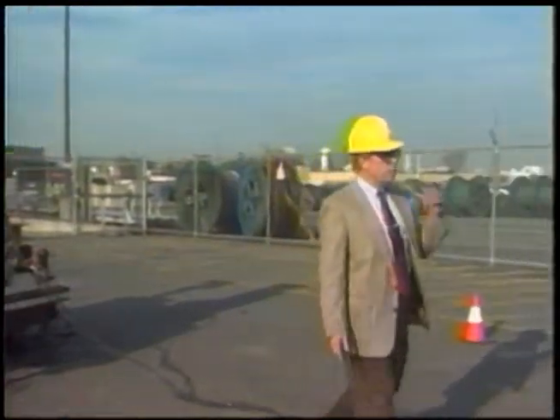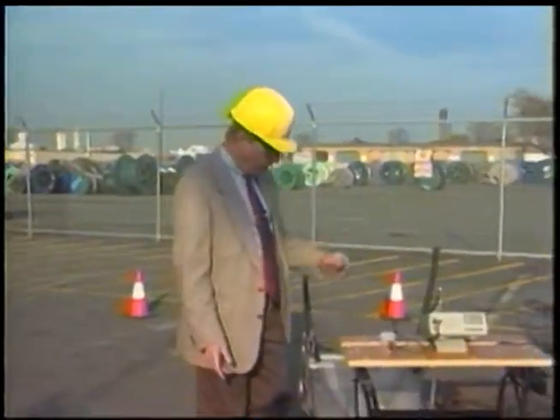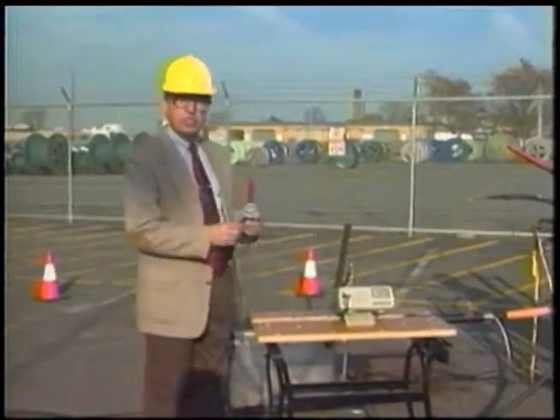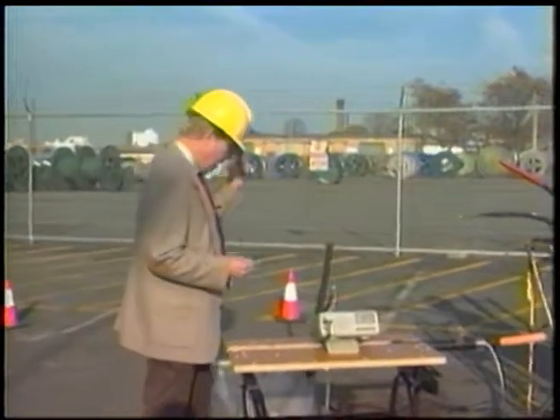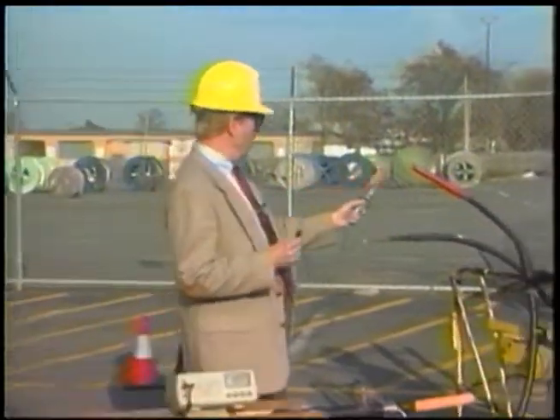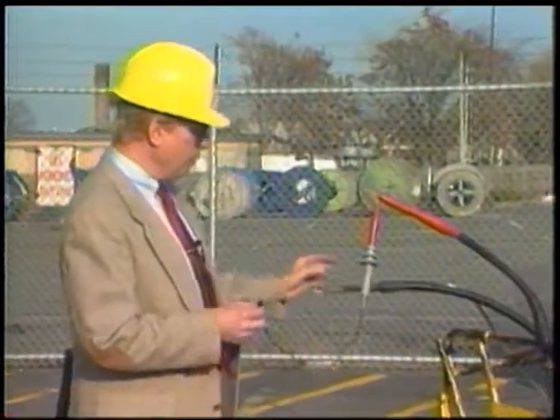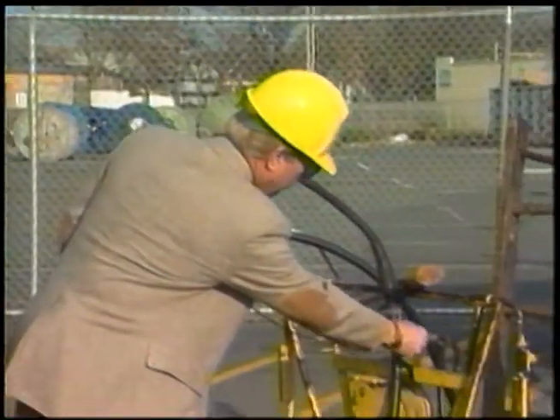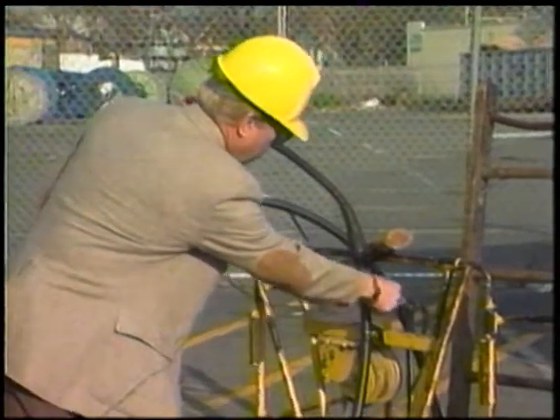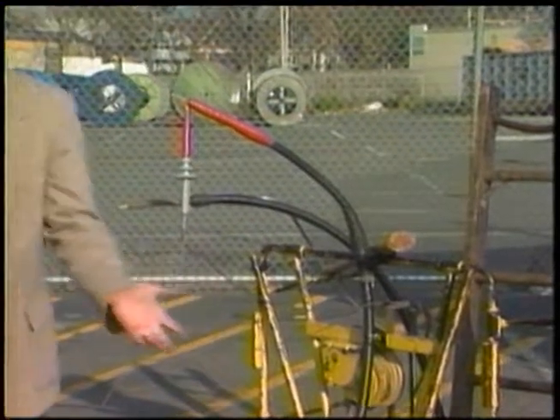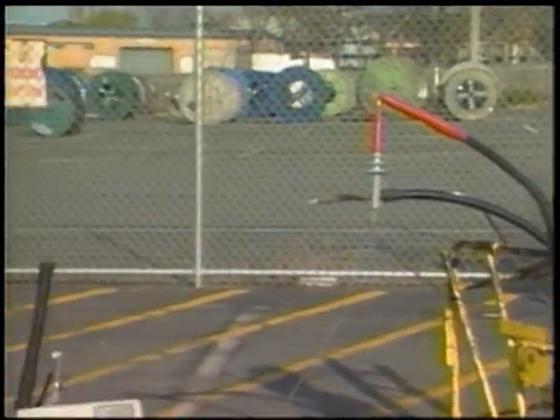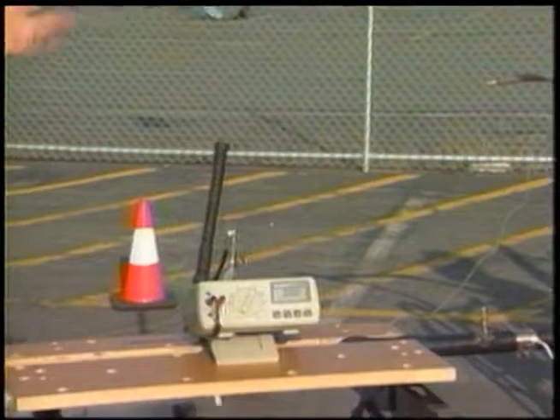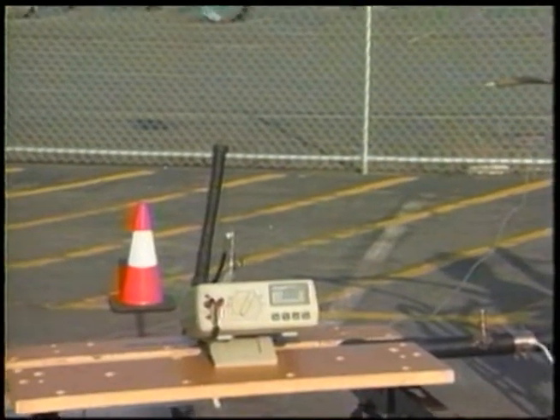In order for us to measure that voltage, to see if we truly have 8,000 volts, I'm going to use this 1000-to-1 probe. The 1000-to-1 probe is going to be placed on the conductor of the cable and to the ground that wraps around the cable. What I'm going to do is step away here to one side and ask Dennis to energize the transformer.